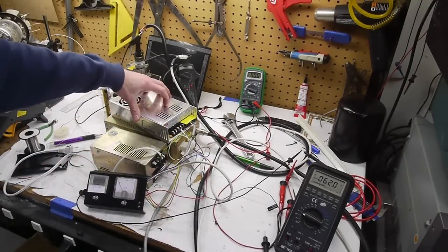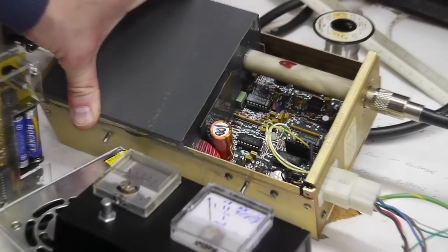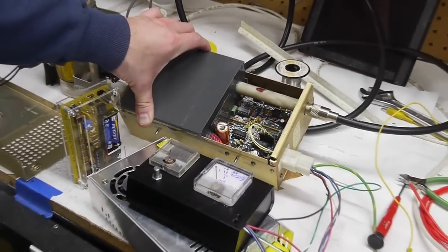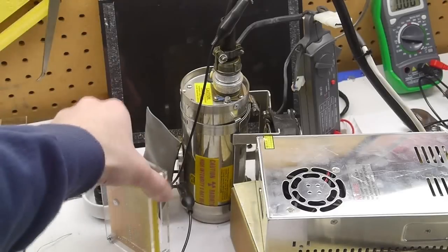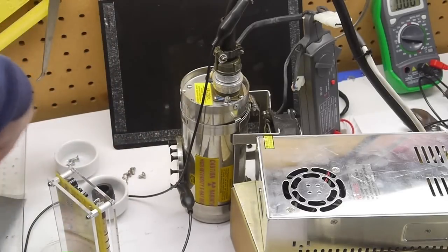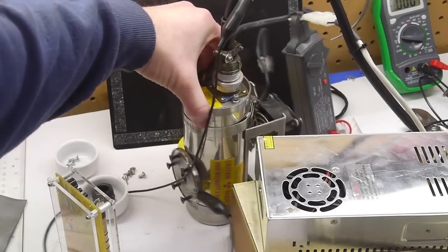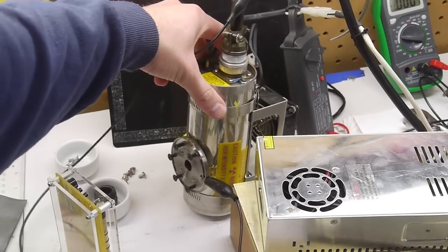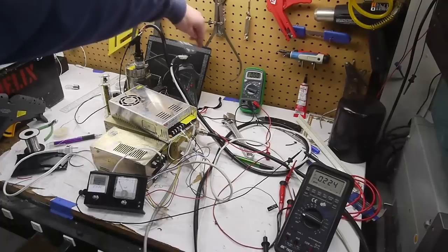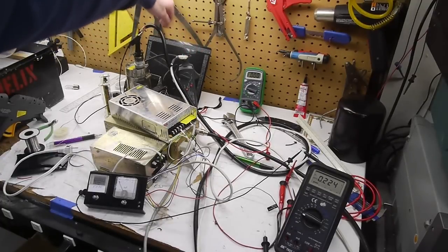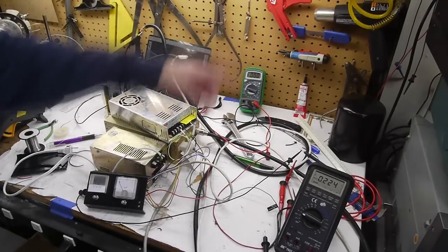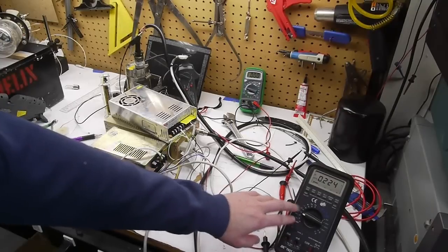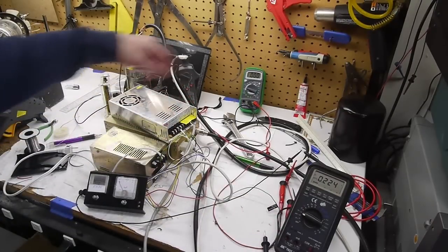So this is a 28 volt switching power supply that powers the 50 kilovolt high voltage supply for the tube. The x-ray tube itself is back here. And it has a lead plate in front of it that's kind of cracked open a little bit with the Geiger counter sitting next to it so we can tell if there's x-rays coming out. I've got my current probe clamped onto one of the filament lines and that will show amperage here.